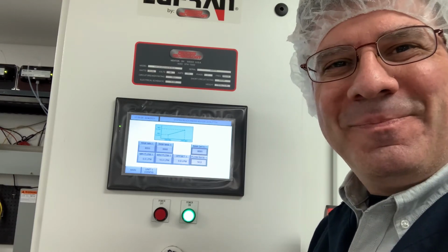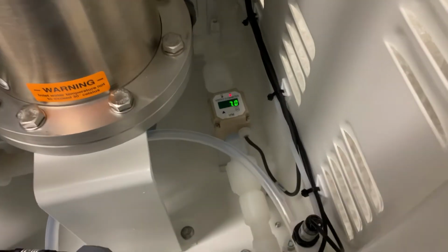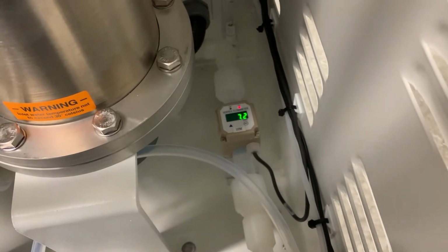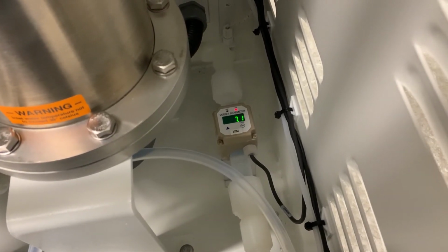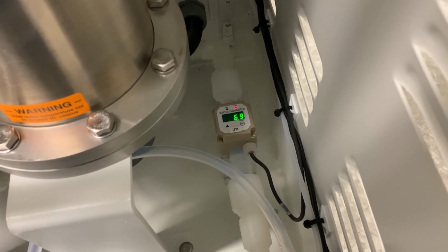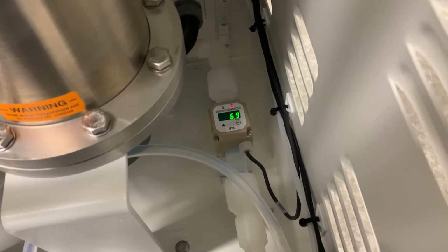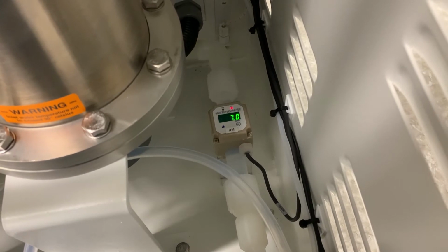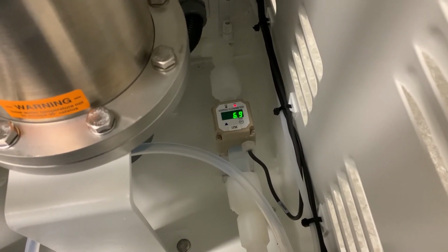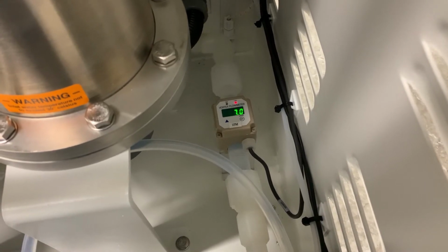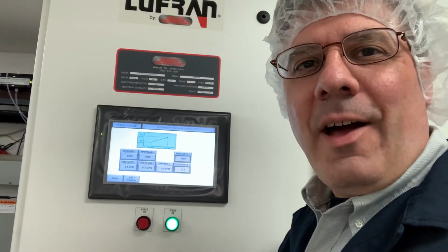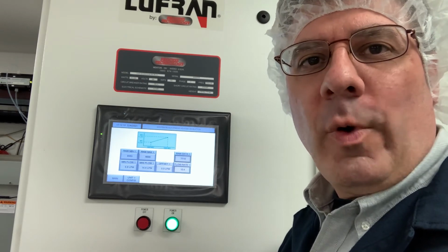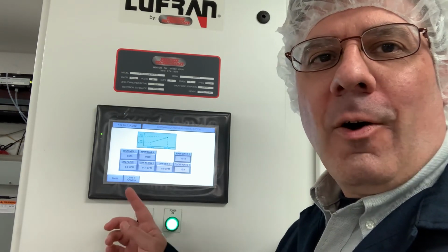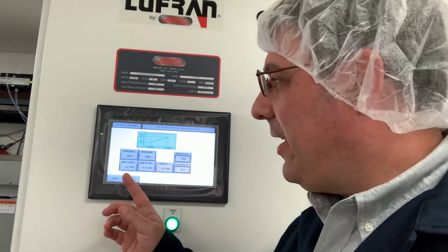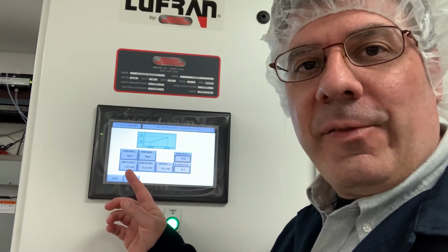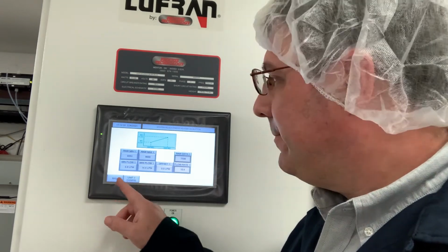Let's go do that now. There it is, between 6.9 and 7.0 liters per minute. That's pretty good. Let's see if our display is within about 0.2 liters per minute. Now that we've established our low-end operating flow rate, we're going to enter the value over here where the low flow value settings are. The value back at the flow meter was 7.0 liters per minute.